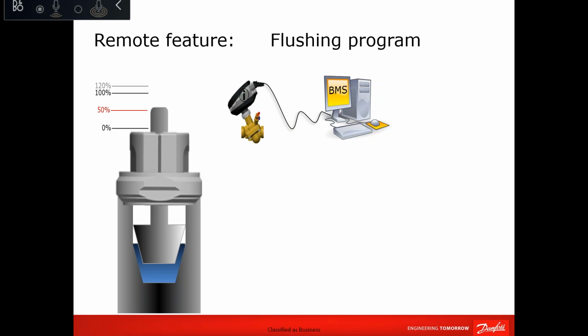So this is also useful in case of testing or pump testing. You can just hit the flush program, it will fully open the system, and then reset the valve again. De-air, this is if you feel like you have some air bubbles stuck inside your valve, then you can hit the de-air to push these air bubbles away from the valve or the coil. So what it will do, it will open and close the valve at max speed 5 times. Once this is done, if there is any air bubble stuck there, it will go away, where the vent valves will be opened and it will come out.